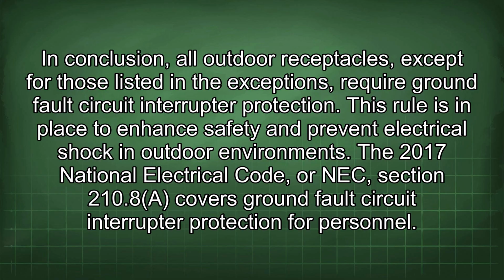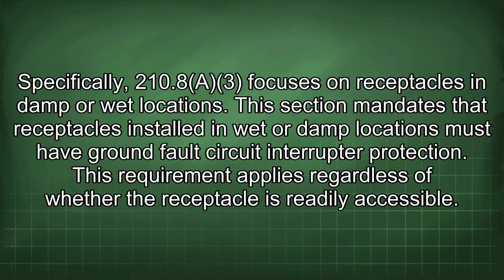The 2017 National Electrical Code, or NEC, Section 210.8 covers ground fault circuit interrupter protection for personnel. Specifically, 210.8 focuses on receptacles in damp or wet locations. This section mandates that receptacles installed in wet or damp locations must have ground fault circuit interrupter protection. This requirement applies regardless of whether the receptacle is readily accessible.